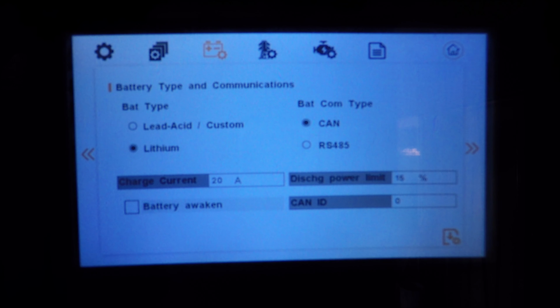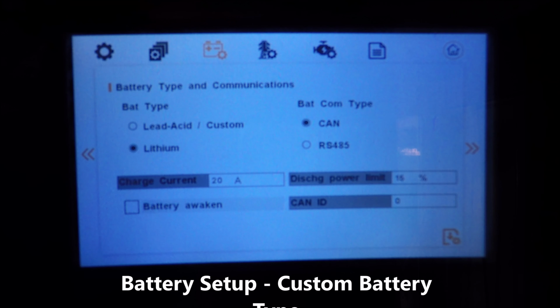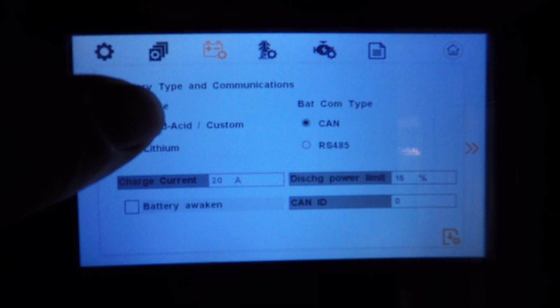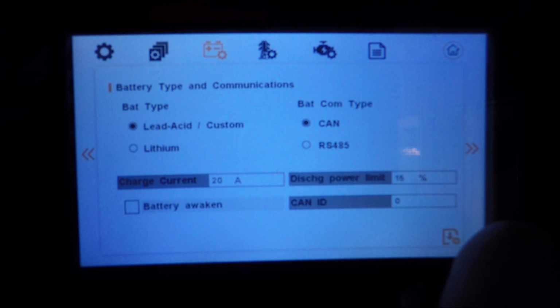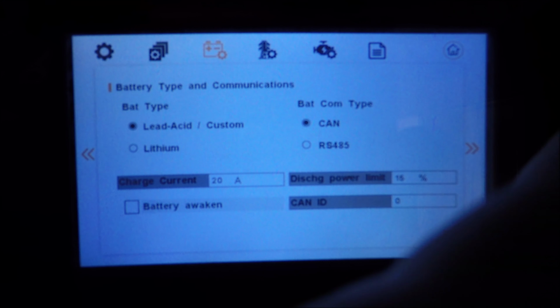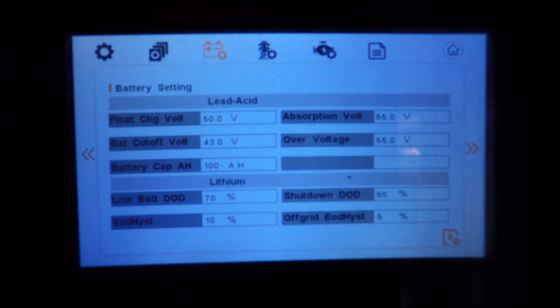Many batteries in their instructions will ask you to set the CAN ID with the DIP switches to 0, and then the next battery is 1, and so on. Sometimes this can cause a communication conflict with the inverter. If you run into a communication conflict, you can double check the CAN ID. Now we'll go over entering a custom battery configuration. I'm going to select lead acid custom. I'm going to save that setting, and I'm going to move to the next screen.